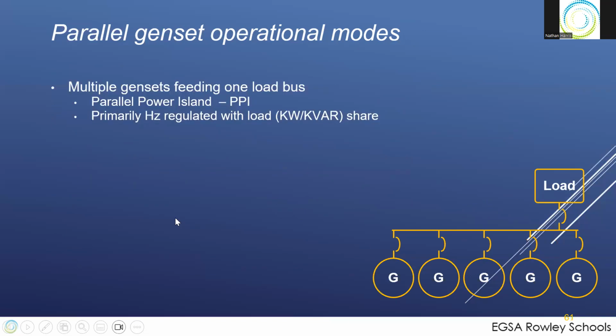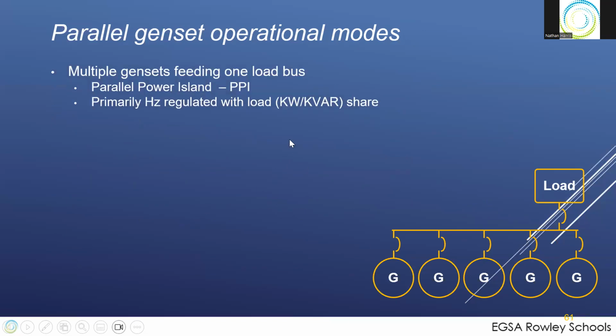So the next is if you have parallel generators feeding a load. So this is a parallel power island feeding. Now, this may not be one load. Okay, this may not be one load breaker. It may be 30 load breakers, but it's one load. There's no other source in the system. Although we consolidate it for this discussion all into one breaker at one point. Again, it might be 30, 40 breakers. We don't know, but it's one set of generators driving the load.